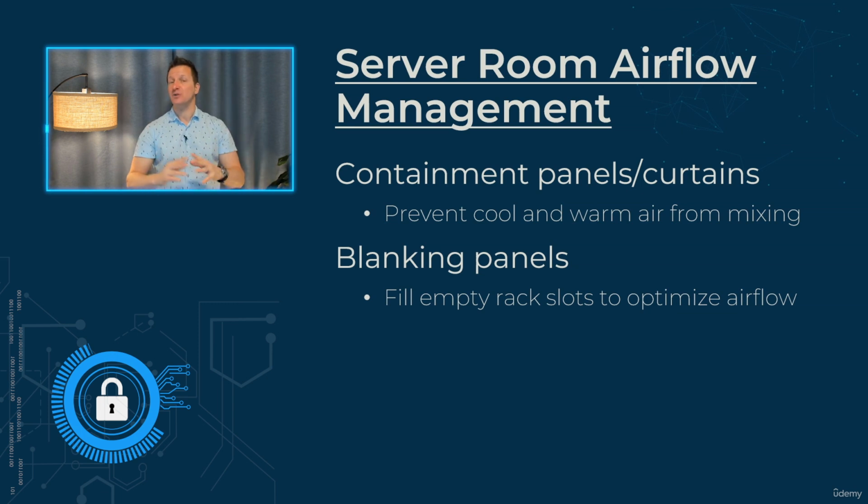If you've ever set foot in a server room or a data center, you've probably seen a lot of cases where in a rack of equipment, if you don't have something slid into one of those areas in the rack, you can have blanking plates that you put there instead. Now, why would I do that? Well, you do that not just for aesthetics, it's really more about controlling airflow. We want to optimize airflow. Again, we don't want to mix incoming cool air with warm air that's being exhausted.